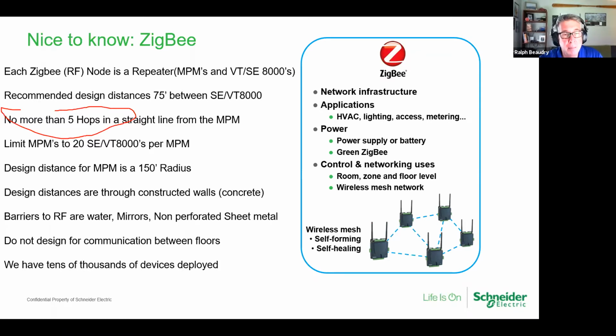I already mentioned 20 8000s per MPM. The MPM itself has a higher power radio. It's got a 150-foot radius that it communicates to. So your first room controller could be 150 feet out, then you go 75, 75, 75. It's rare that we see a job like that. More typically, you're going to want to put the MPM in the center of a cluster of room controllers. So you're doing a wing of a building, you got 20 rooms, 5 rooms down into that wing, you're going to throw an MPM in the center of that cluster. And then you're probably going to take an Ethernet cable from that MPM and bring it into a switch and back into your network level controller, whatever that is, right? That's what your architecture is going to look like.